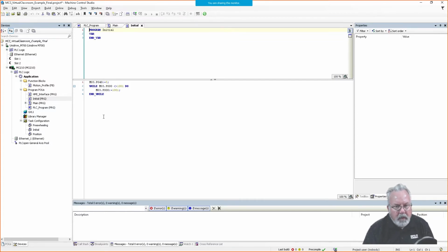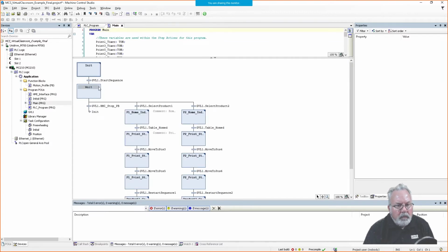And the point again being with the initial POU, this is used so that if the host drive fails, these control modules very rarely have problems. So you just unplug the control module from the drive that's having a problem, replace the module back onto the new drive, and on PowerUp, the initial POU will commission the drive in its entirety, and away you go. So that's the initial task in the initial POU.